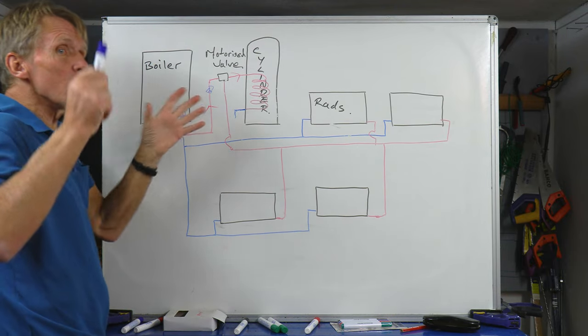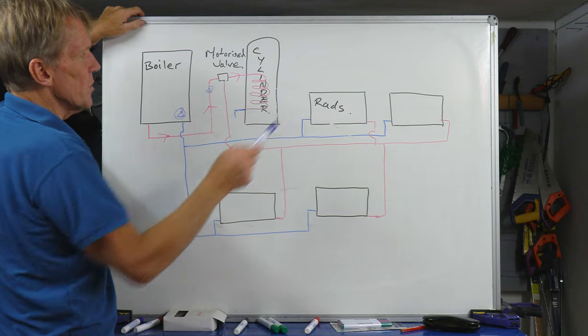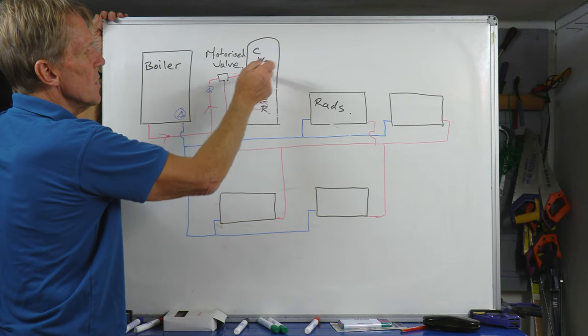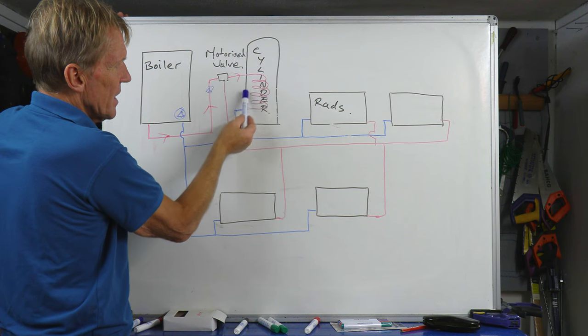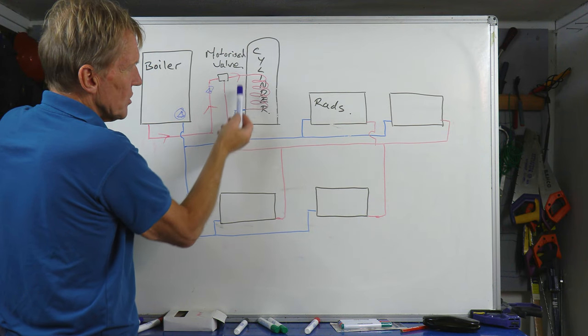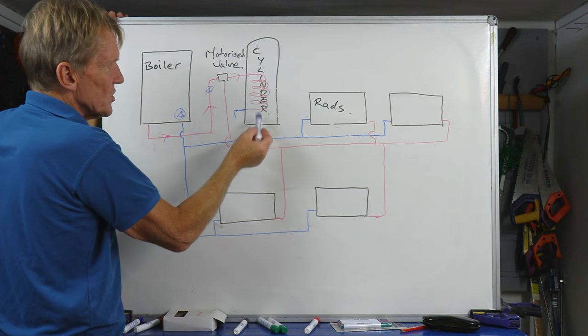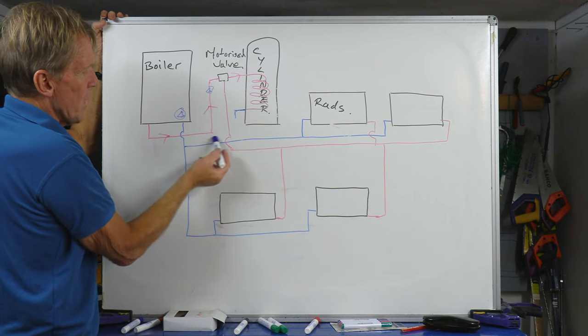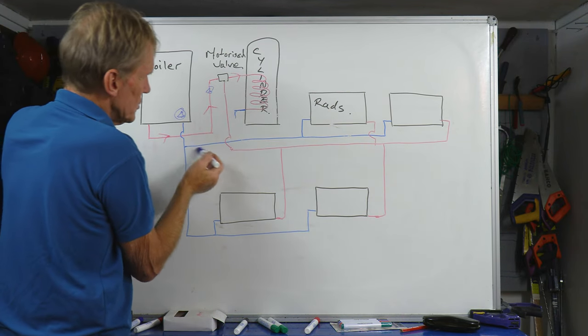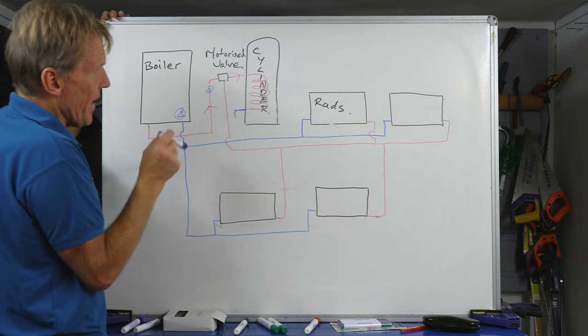Now the motorized valve is where it splits up to go through to the radiators, the central heating, or it goes through to the cylinder for the hot water. That water inside the cylinder is in a coil so it's not mixed with the tap water. It goes through the coil which transfers the heat to the water which comes out your taps, and then it makes its way back to the boiler, which I haven't joined up at this moment because I want to explain something about that.